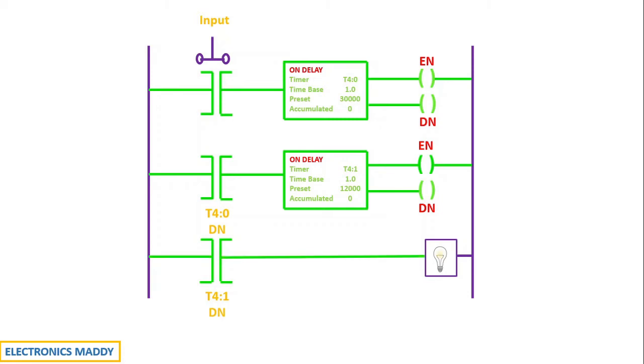Now, the rung gets energized and the current starts flowing through the load and the light starts glowing. So, what are we able to achieve in this case? We are able to achieve a 42,000 second delay by using two different timers. And this concept is called cascading.